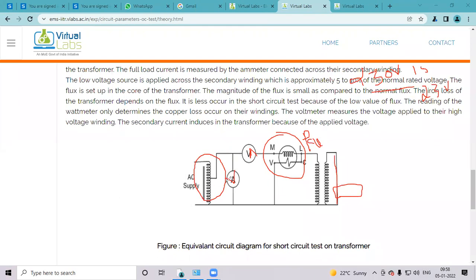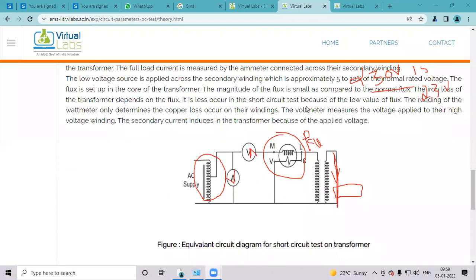Here we are not applying rated voltage, we are applying near about 5 to 10% voltage to pass the rated current in the transformer. Through the transformer's secondary side, we apply just enough voltage so that rated current flows. So this is the short circuit test.